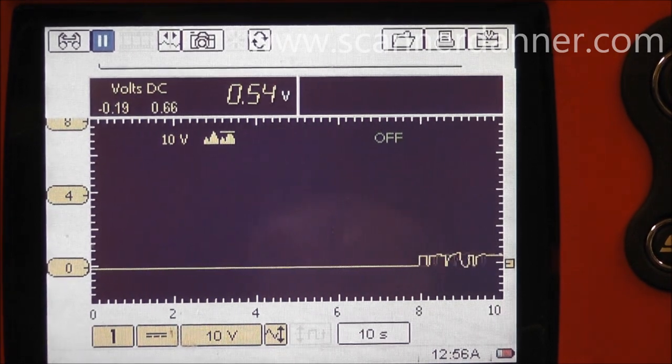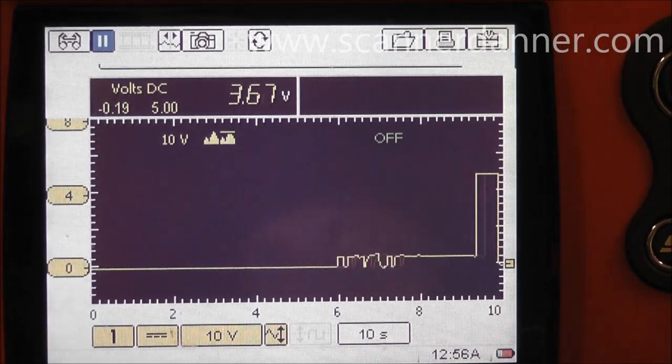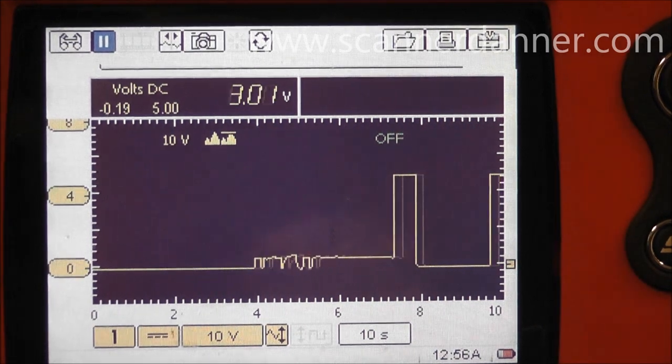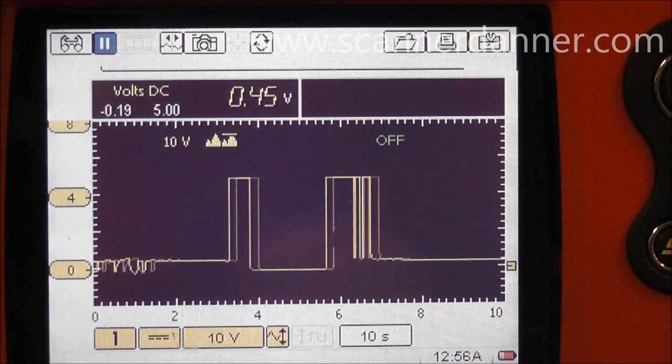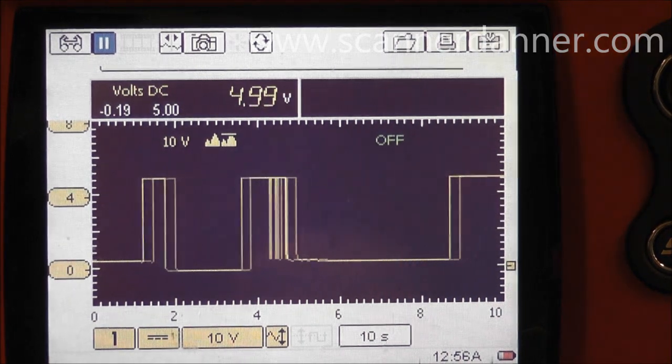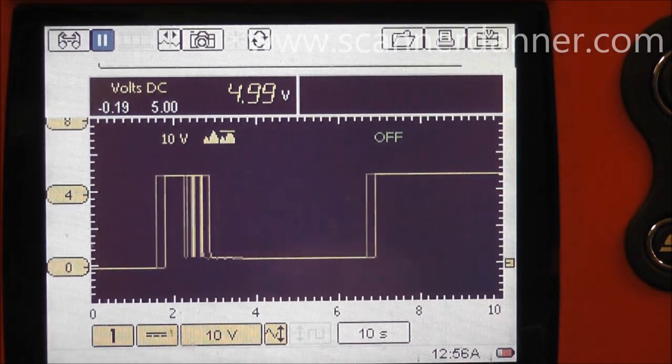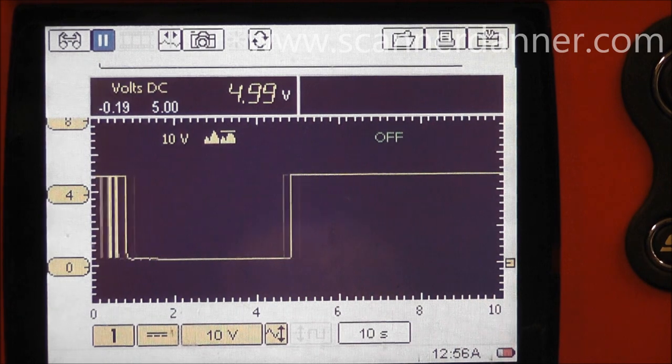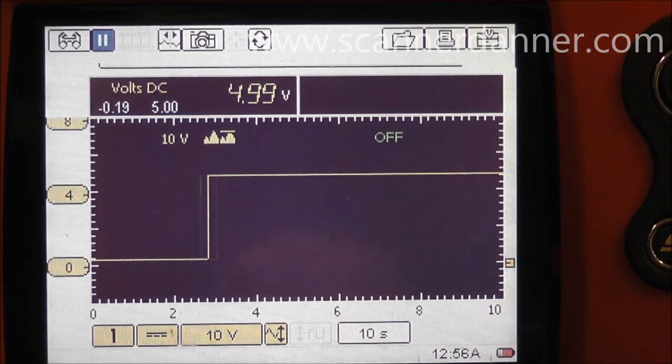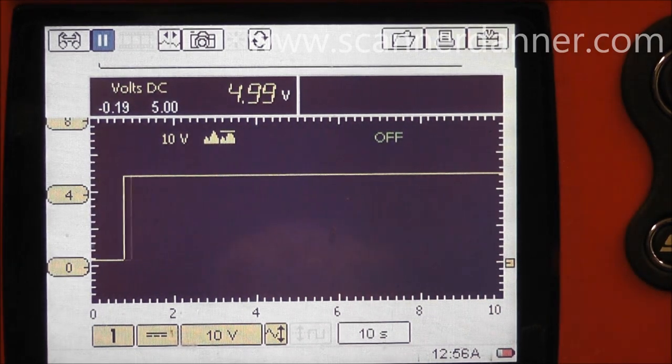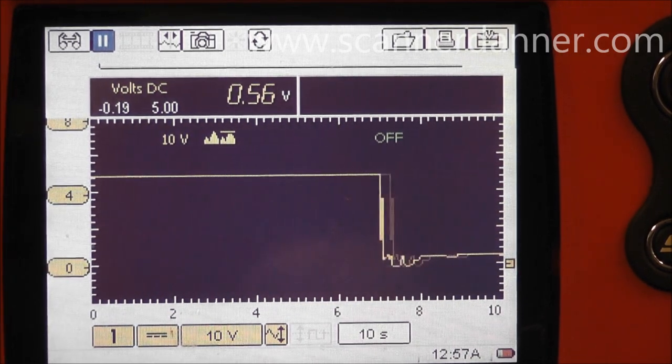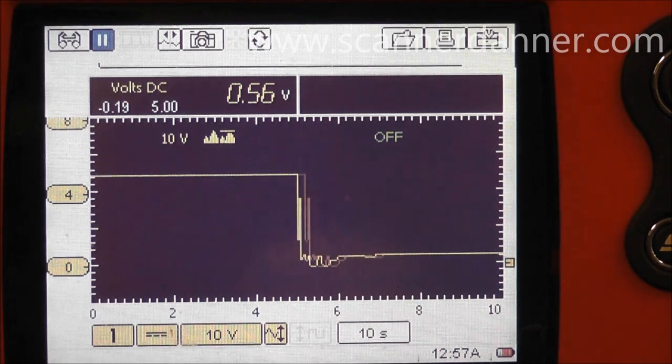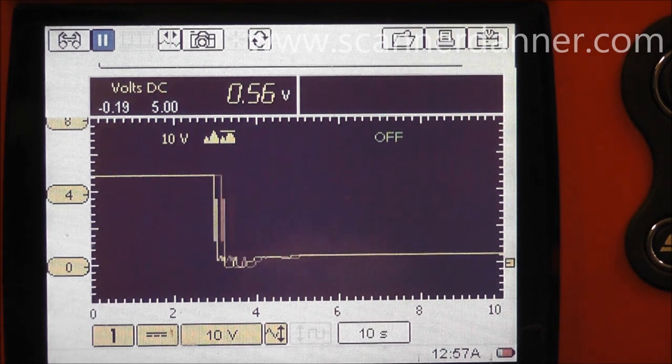Same thing on the reference wire, which is the bottom wire. And this one should be a steady five. And we want to do the same kind of tests. Some snap throttle. We don't want to see any drops or anything in that reference wire. And that looks pretty good. So I'm not concerned about the connector. I'm not concerned about the five volt reference and the ground.